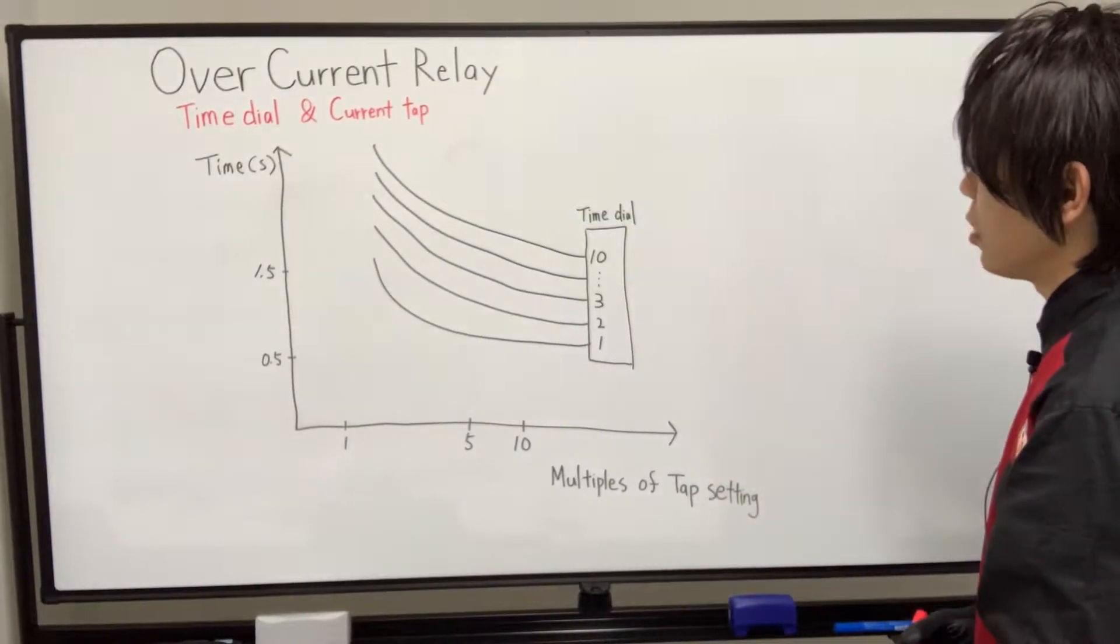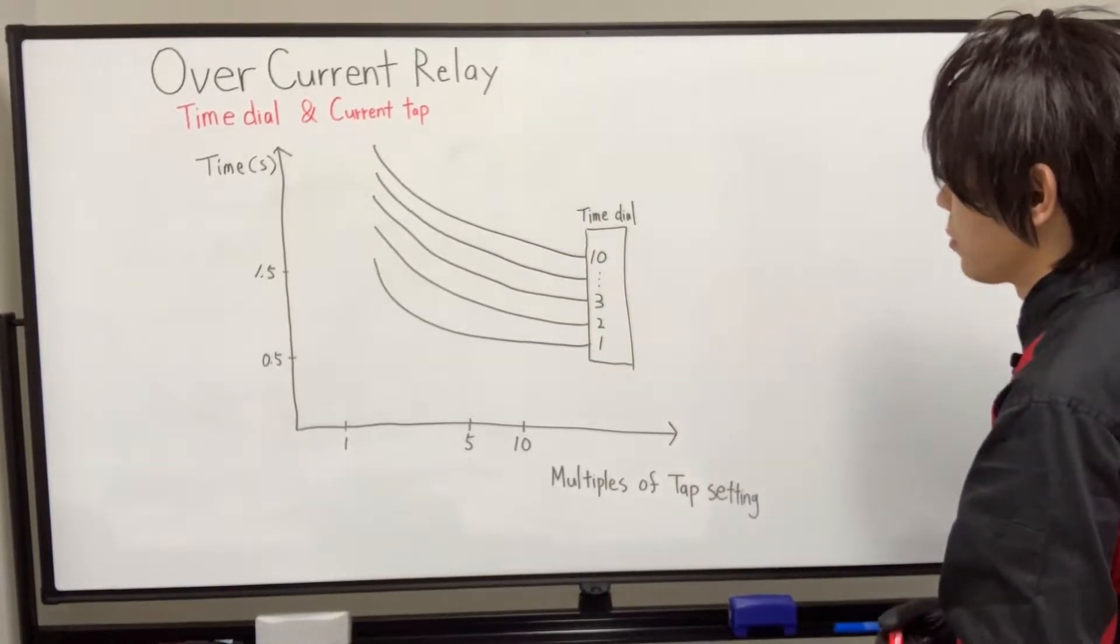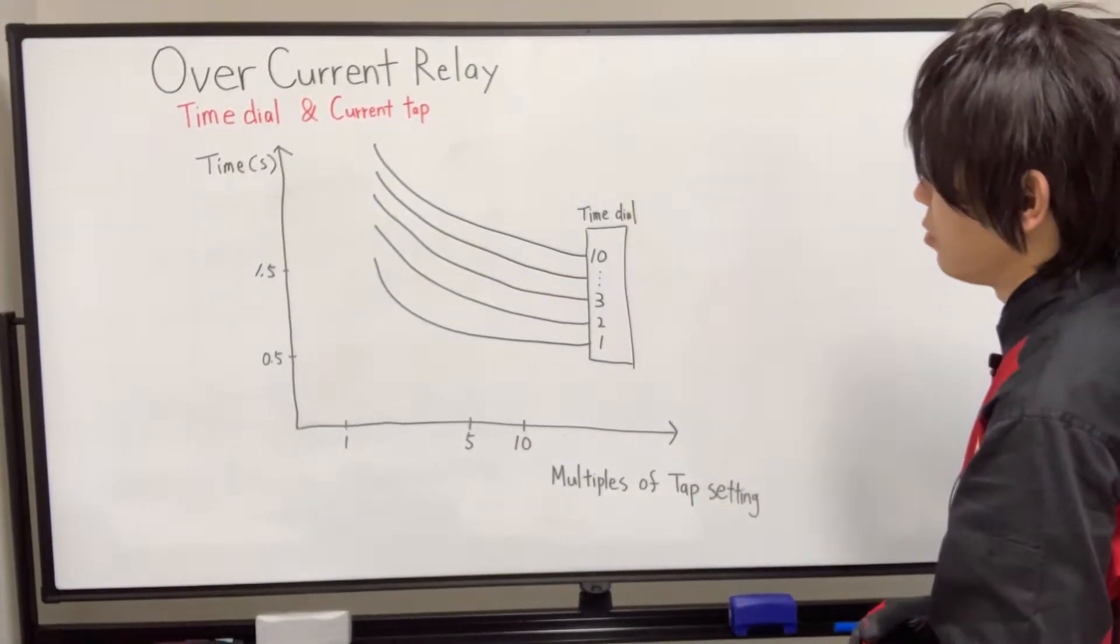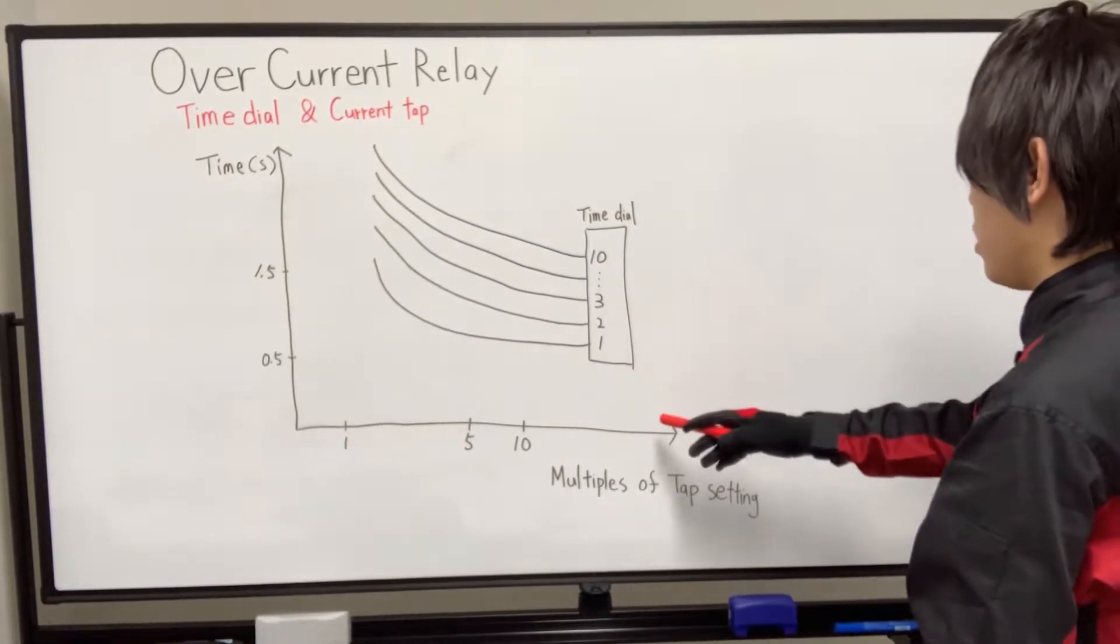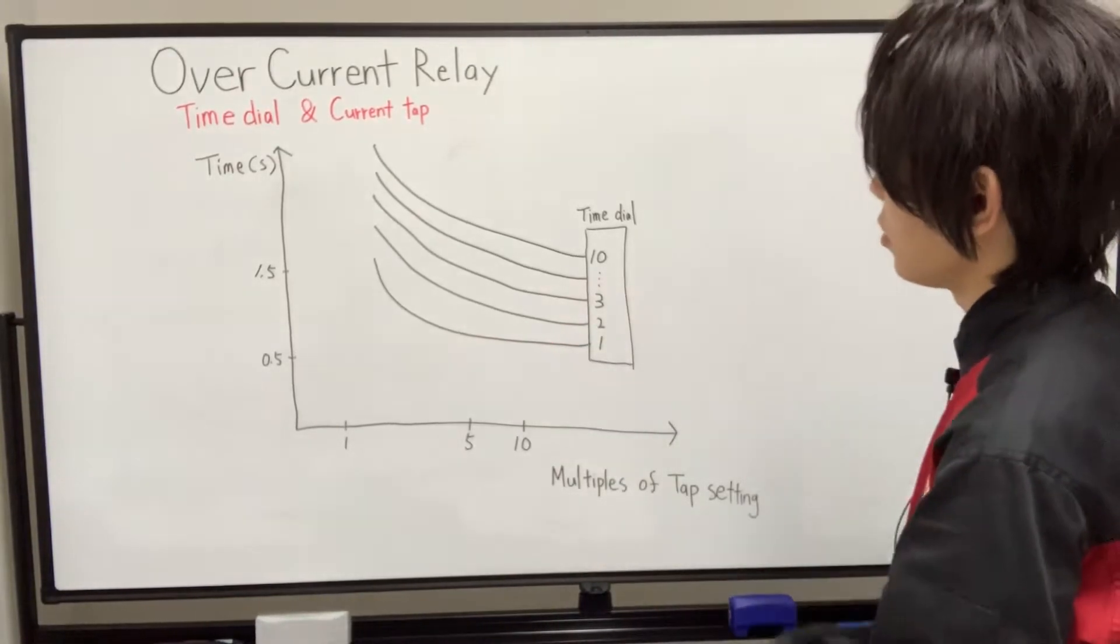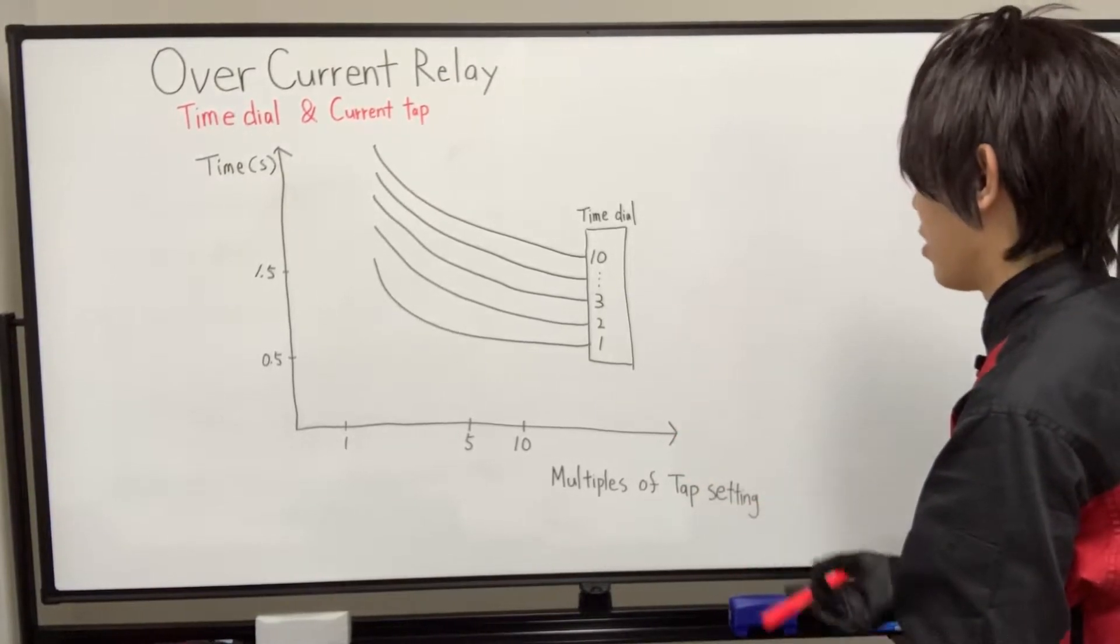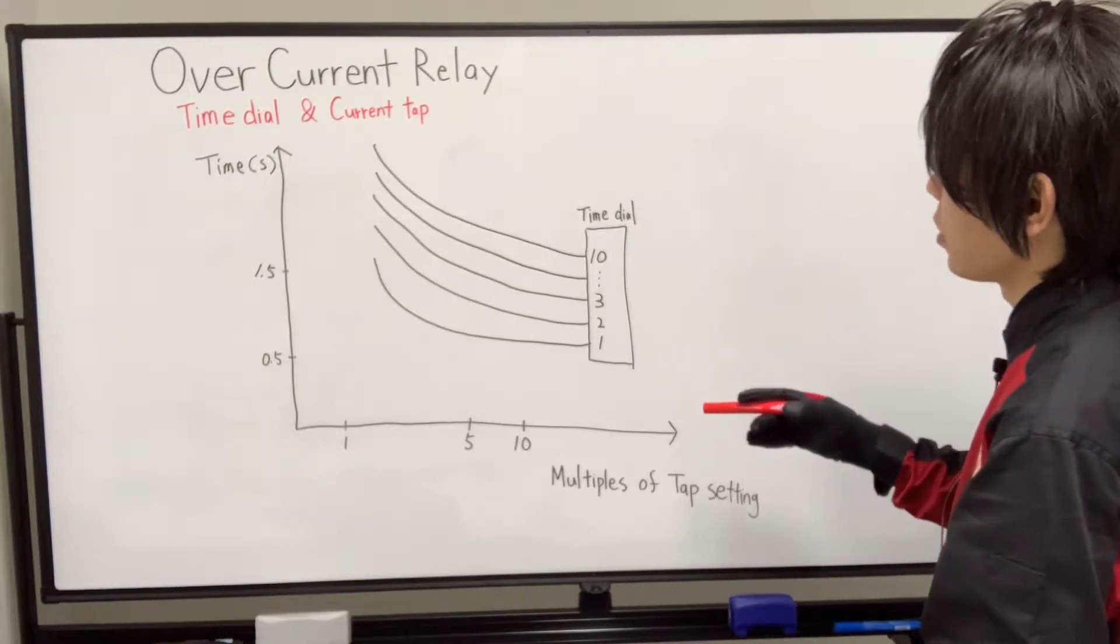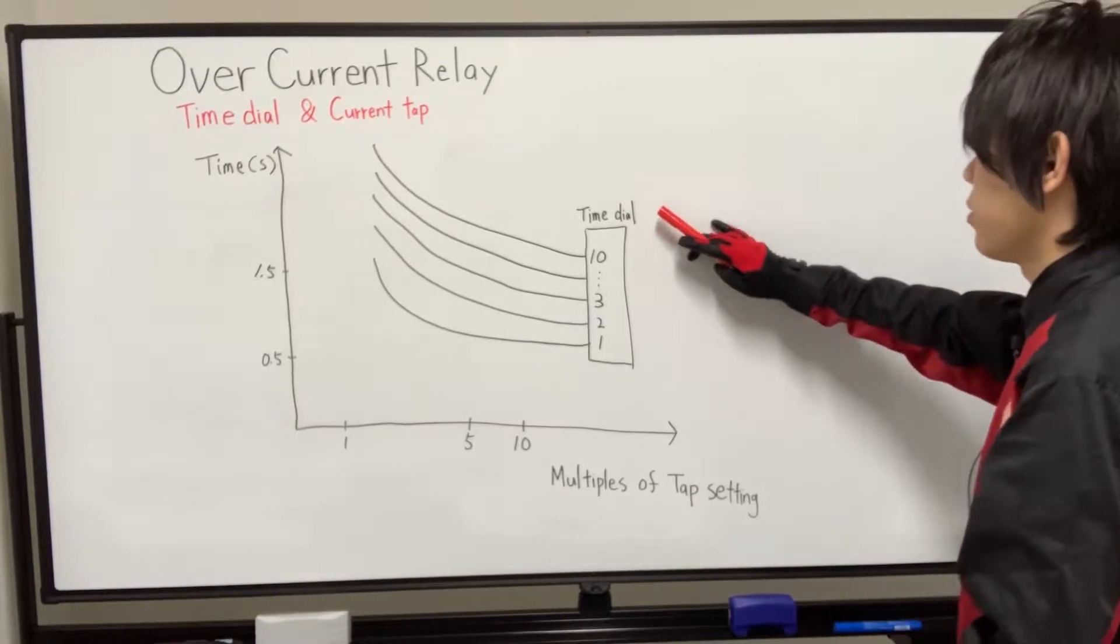These are well-known inverse time characteristics shown as this family of curves. The time for overcurrent relay's contact closure is shown on the vertical axis. The higher the level of fault current, the quicker the operation of the relay. Moreover, at any particular current level, we can adjust the operating time by adjusting the time dial.